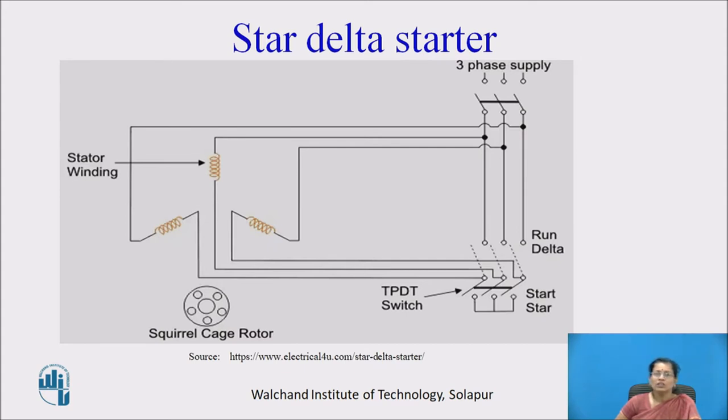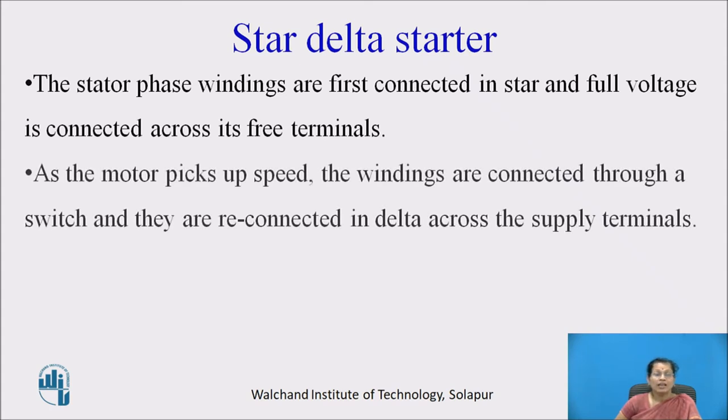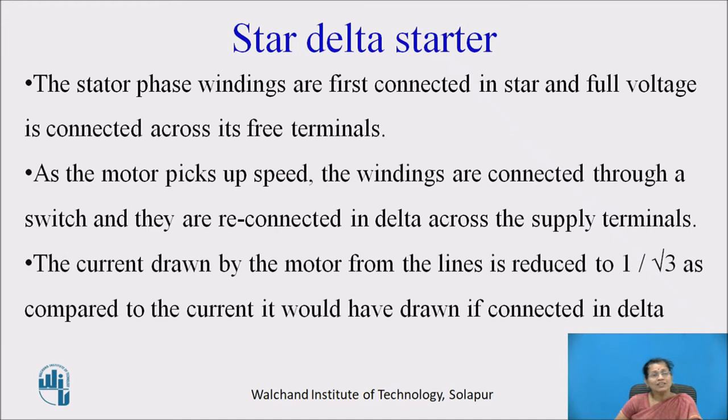Let us see how the reduced voltage is given to the motor. The stator phase windings are first connected in star and full voltage is connected across its free terminals. As the motor picks up speed, the windings are reconnected in delta across the supply terminals through a switch. The current drawn from the line is reduced to 1 by root 3 compared to the current drawn if connected in delta.